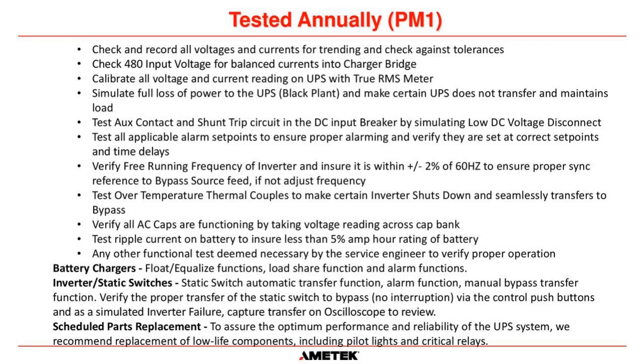We have 2 circuits within the synchronizing circuit of a UPS. One, when you have bypass available, it will synchronize itself to the 60 hertz signal from the bypass. When the bypass voltage and frequency is lost, then what happens is the inverter starts running on its own internal clock. It actually has a quartz crystal inside the control board that is designed and set up. If it has no external signals, it will run at exactly 60 hertz in America and obviously 50 hertz in some of the other international countries. And those 2 circuits are different. So we always test the free running frequency of the inverter to make sure if you do have a bypass failure, that it does operate still at its correct frequency.